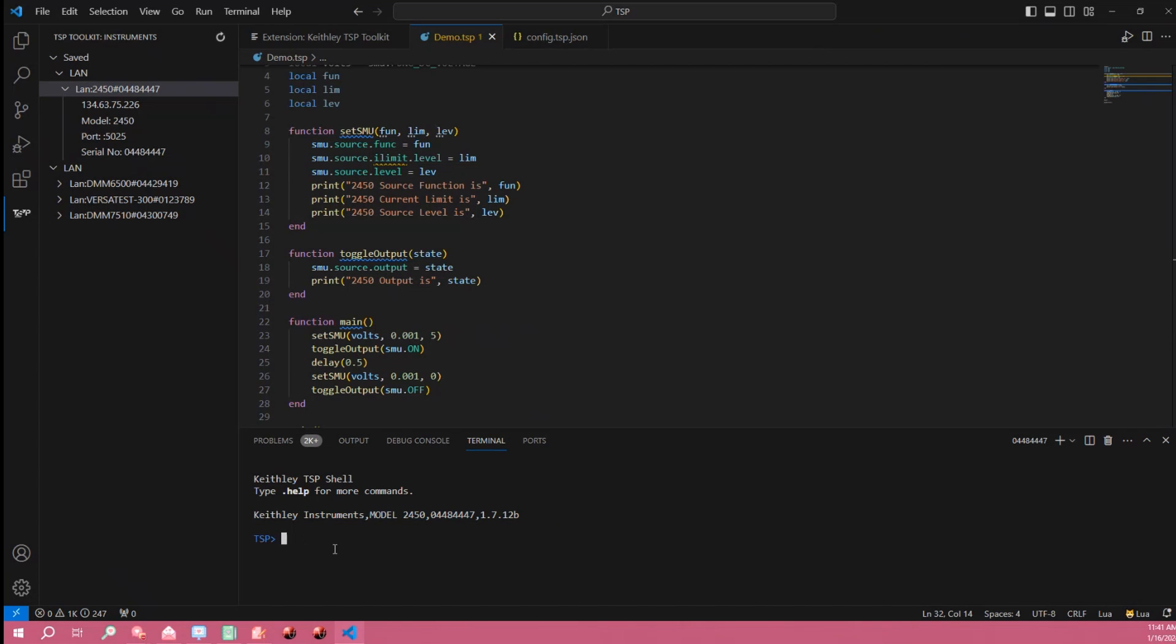So this terminal down here works like any other command prompt where you can send instrument commands to the instrument directly such as star IDN and then get a response.